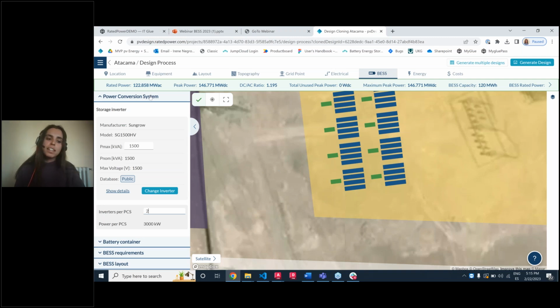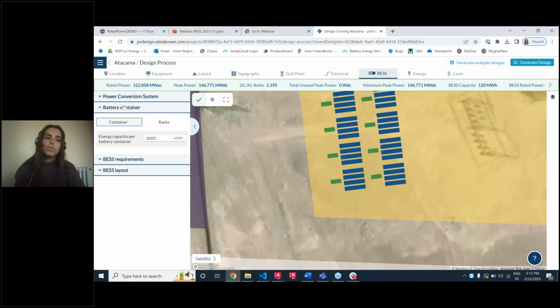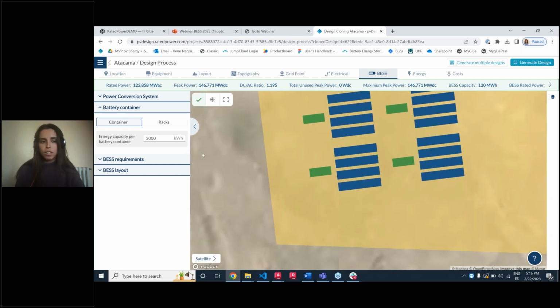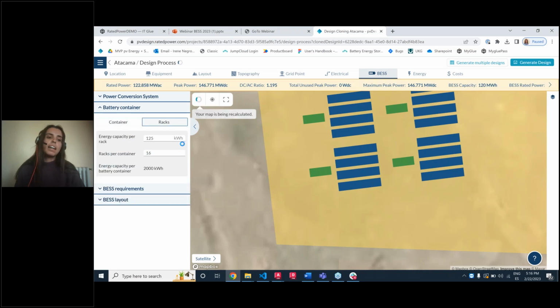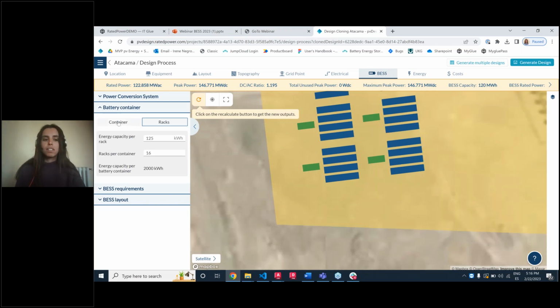Once we have set the power of our block, the next step is to define the capacity of the battery containers. We have two possible solutions: you can set the capacity per complete battery container, or you can define that capacity per rack and then set the number of racks per container, and that way we would be sizing the capacity of our battery.